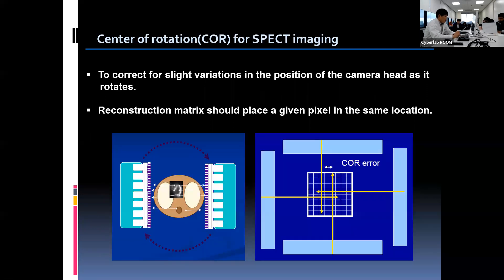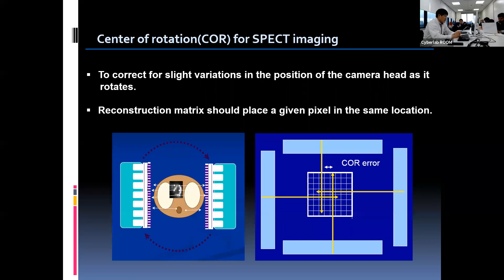Now we are going to look at the COR test and tomographic phantom study, which are the tests to monitor the SPECT system. When you perform SPECT imaging, the camera has to rotate for three-dimensional acquisition. If the rotation is perfect, the reconstruction matrix will always place a given pixel in the same location. To check and correct for slight variation in the position of the camera head when it rotates, COR evaluation needs to be performed.